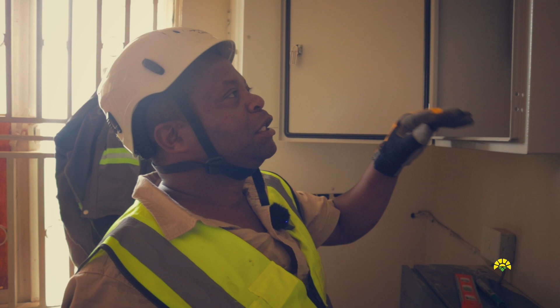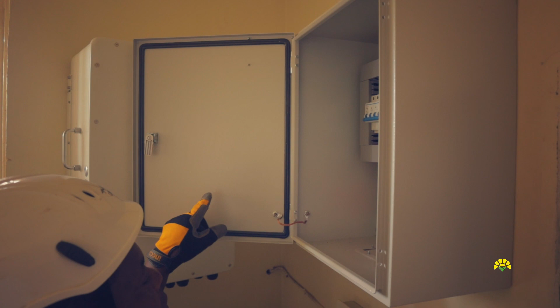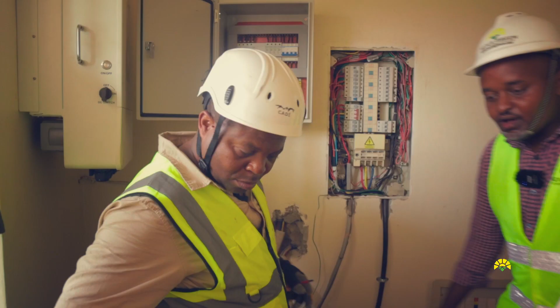This metallic part is loosely attached because of the hinges. Now we need a solid earth that runs from one metallic part to another, that's why we have this cable here. From here it goes to the bus bar. Then from the bus bar there's a cable that comes from the OVR, and we will have the final earthing going to the ground.